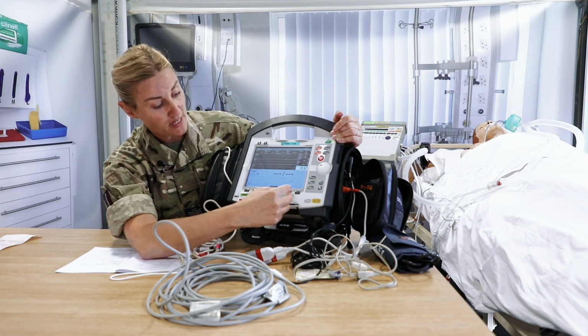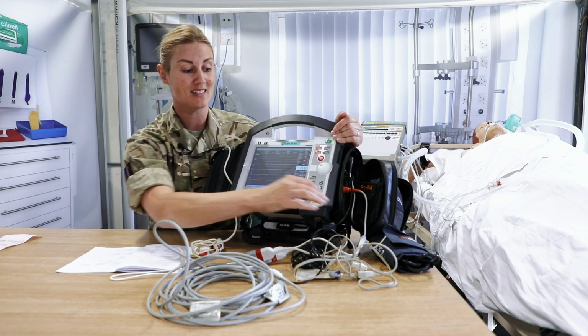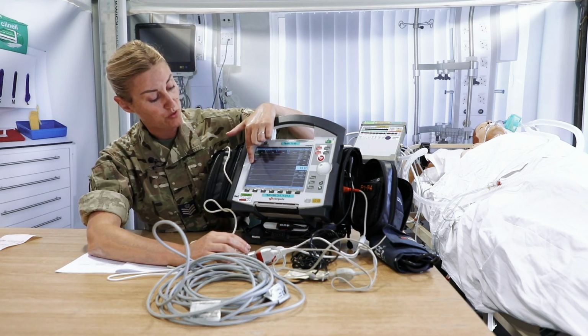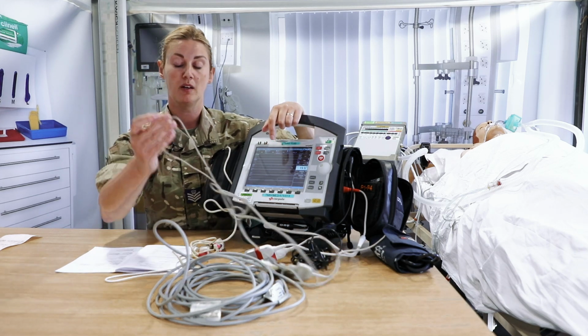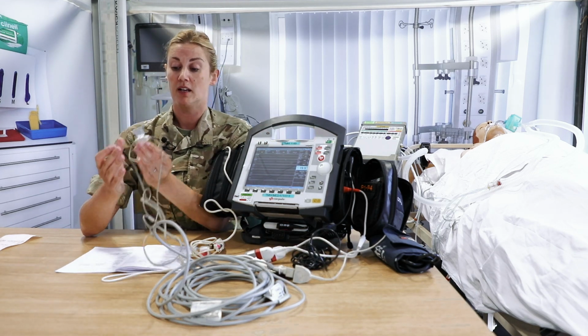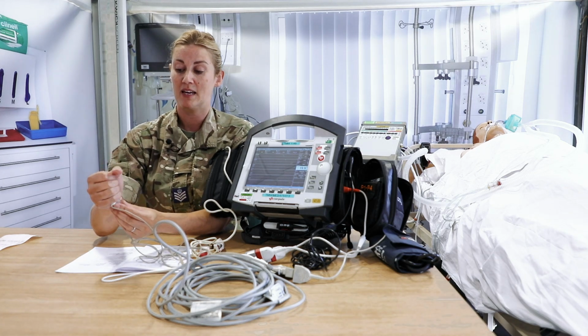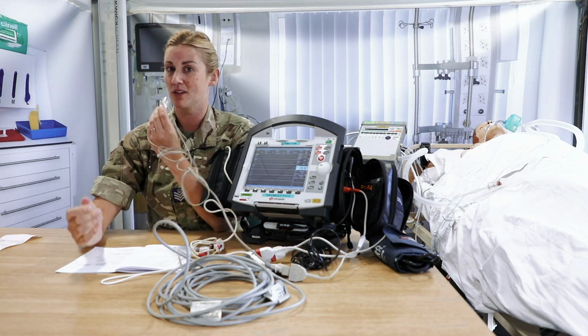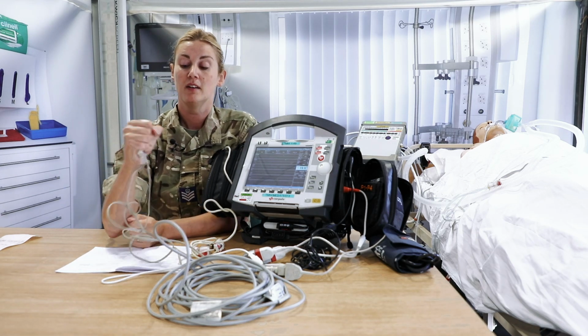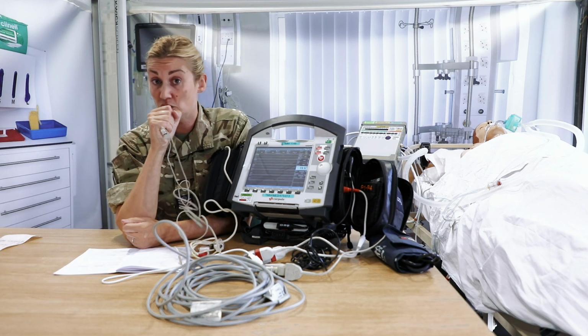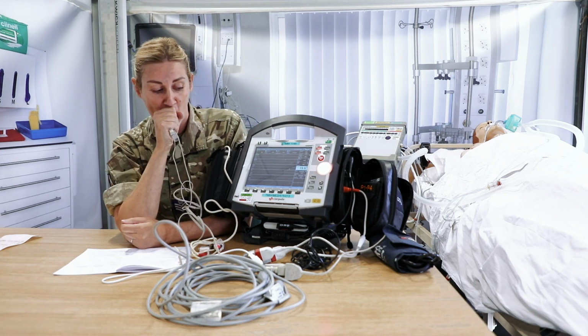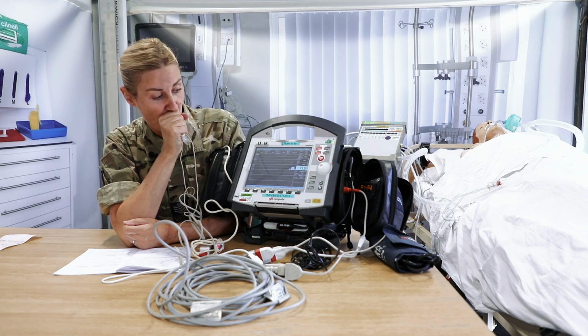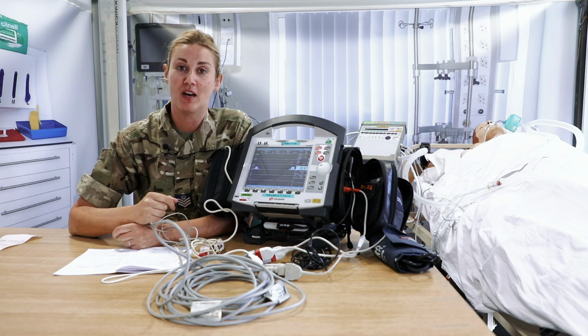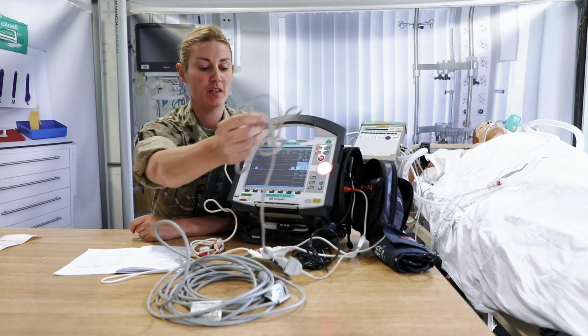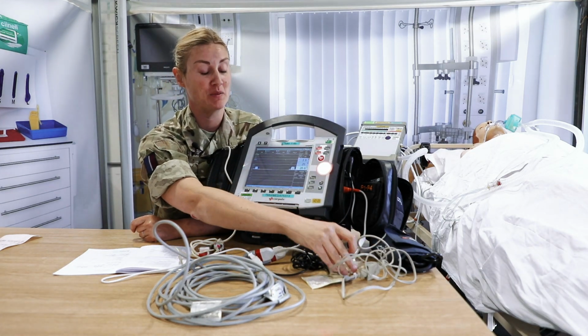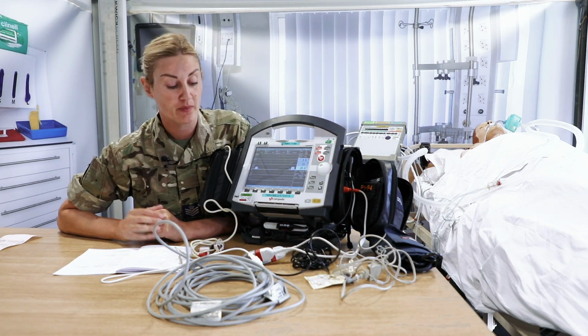So once the blood pressure is taken, I would recommend closing that, just because you need to now be able to see the end tidal CO2 pressure wave. To check the end tidal CO2, connect up your cuvette, and then I would just place my hand over the cuvette, because I don't actually want to stick this thing in my mouth, because multiple people have done that. So just place your hand over the cuvette and just literally, all you're going to do is blow. So blow into the cuvette and confirm that you have a waveform. This will alarm at you because it thinks it's been disconnected, but just ignore it from now on.